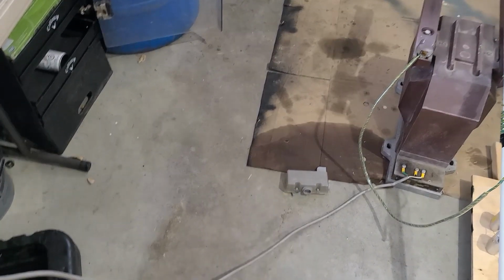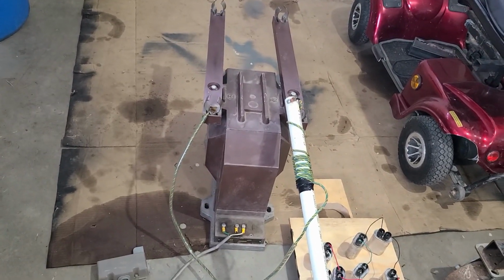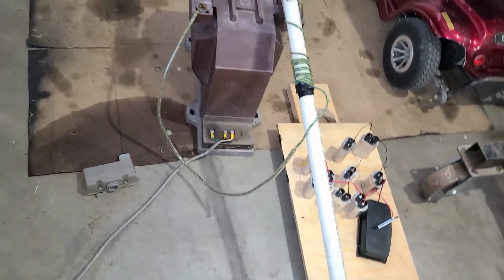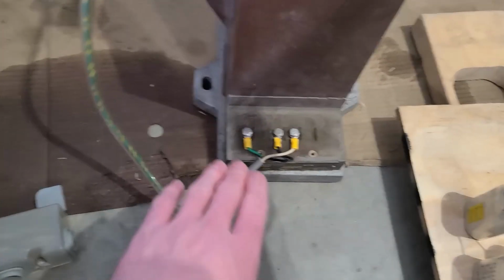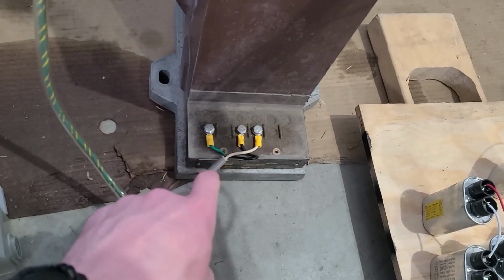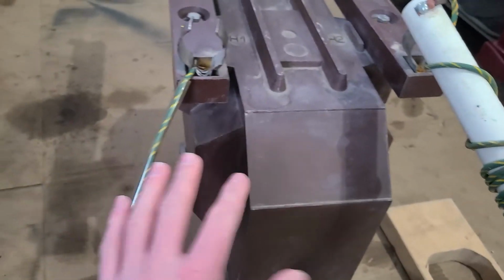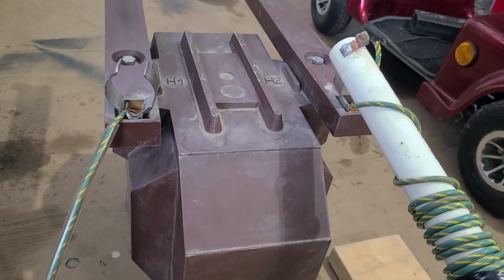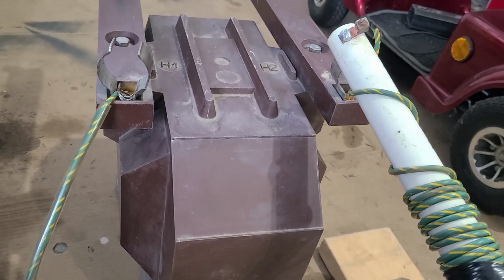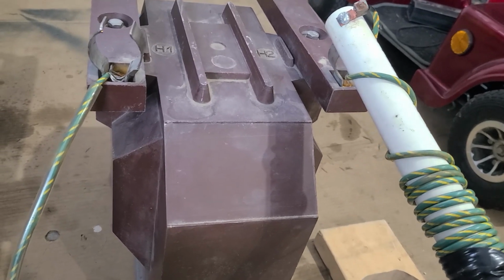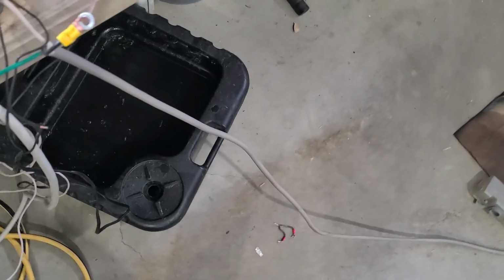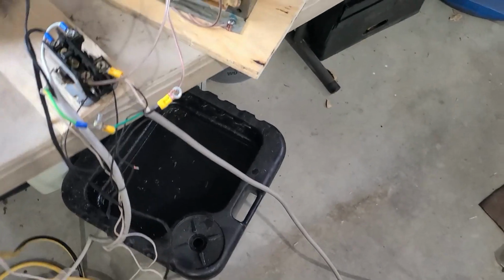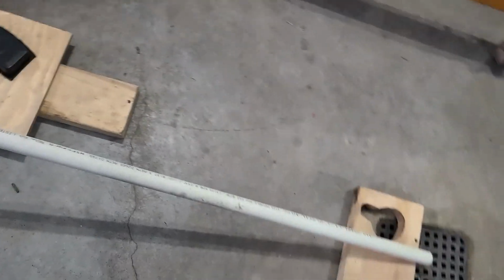So it's a dead man switch, it's momentary. This is not grounded - only the secondary side with the low voltage is grounded. The primary side is floating completely, so it's relatively safe in that I don't have to worry about it arcing back through the other side. Plus, I have a long chicken stick.